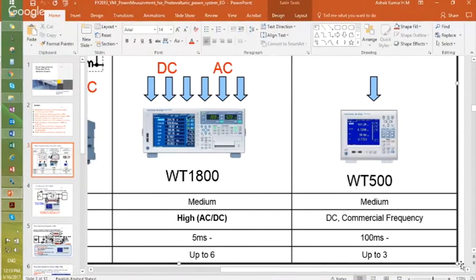Here the variation is minimum, and here it's very high. 0.1% of 11 kV is still huge in terms of 11 volts. If I use 0.01% accuracy, that's 1.1 volts. So even measuring 11 kV, the variation is only 1 volt. For 440 volts with 0.1% accuracy, that's 0.44 volts. So it all depends.